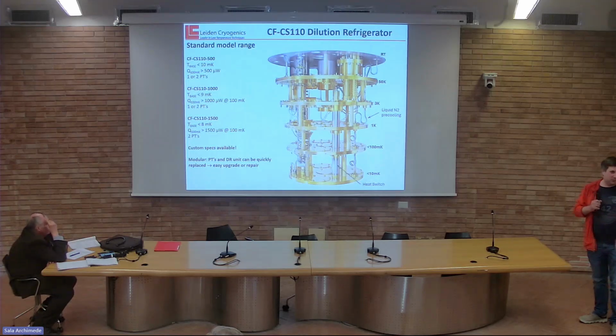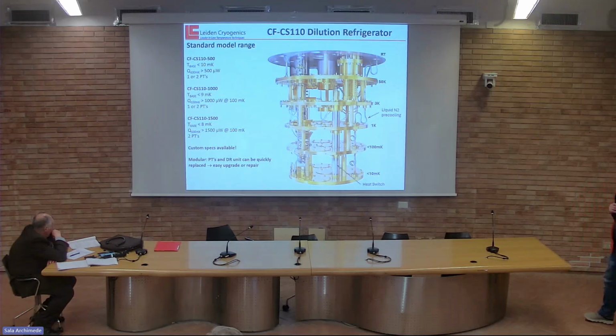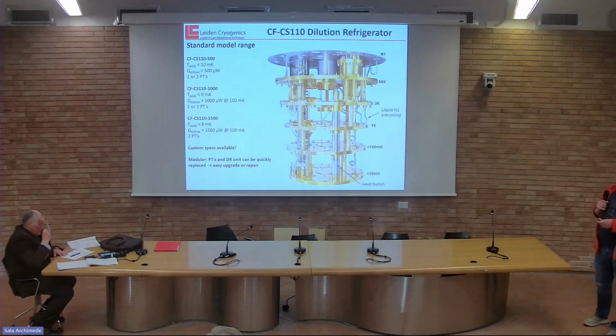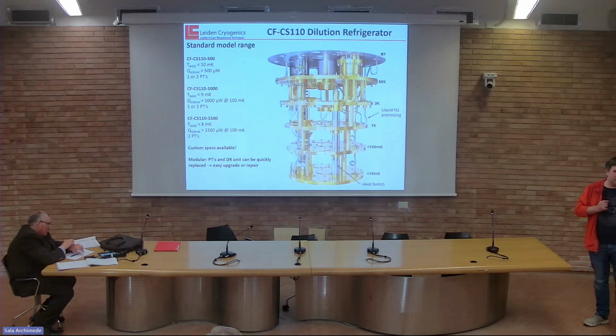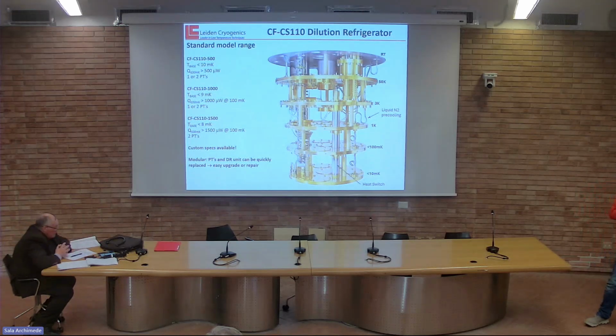model range. We can also offer customized systems with more cooling power, less cooling power, lower base temperature. We're very flexible. And the system is pretty modular. For instance, you can easily add or remove the pulse tube. You can buy a system with 1 pulse tube. And later, if you decide you want to put some electronics at the 3 Kelvin plate and you want more power, it takes 2 hours to add the second pulse tube.